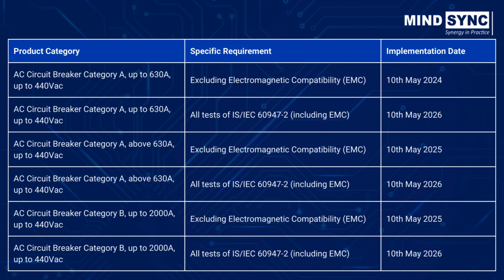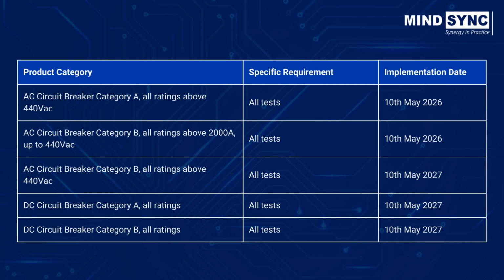Talking specifically about IS 60947 Part 2, that is for molded case and air circuit breakers, where the effective dates are based on testing. So for the 10th of May 2024, any product that is up to 630 amps and up to 440 volts AC, the effective date is May 10, 2024. It is excluding EMC testings and any range that falls under this category, with products that fall under EMC, the effective date only for EMC portion is May 10, 2026.